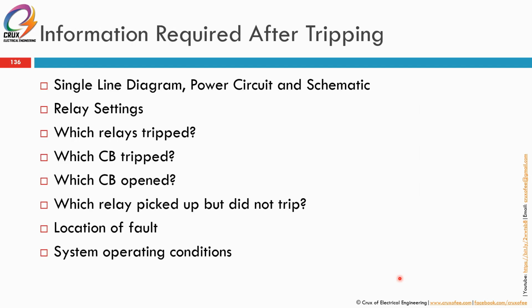Okay, so what information is required after tripping? Obviously the single line, power circuit and schematic. This one you have to know. The relay settings, the relay setting that was triggered, the upstream relay, the downstream relay. So which relay tripped and their settings, which CB tripped, which CB opened, and which relay picked up but did not trip. Also identify the location of the fault. And what was the system operating condition prior to the event? Was it a normal operating condition or not? All this information you have to gather. It will help you in troubleshooting the equipment, troubleshooting the tripping problem.